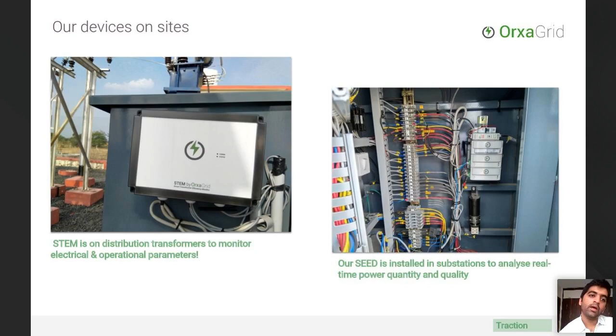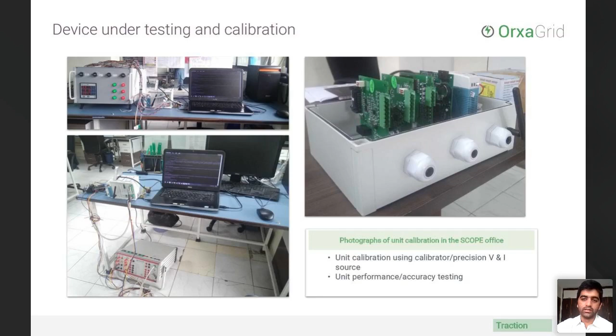A few more photos of our device under testing. This is how modular the device is. It's very similar to the SEED. This is a STEM box which is IP67 protected. We do all our testing through calibrated sources. In this particular photo, we can also see a relay test kit that we have implemented, so that we could run different logics and see how accurately the devices can detect and alert the system.